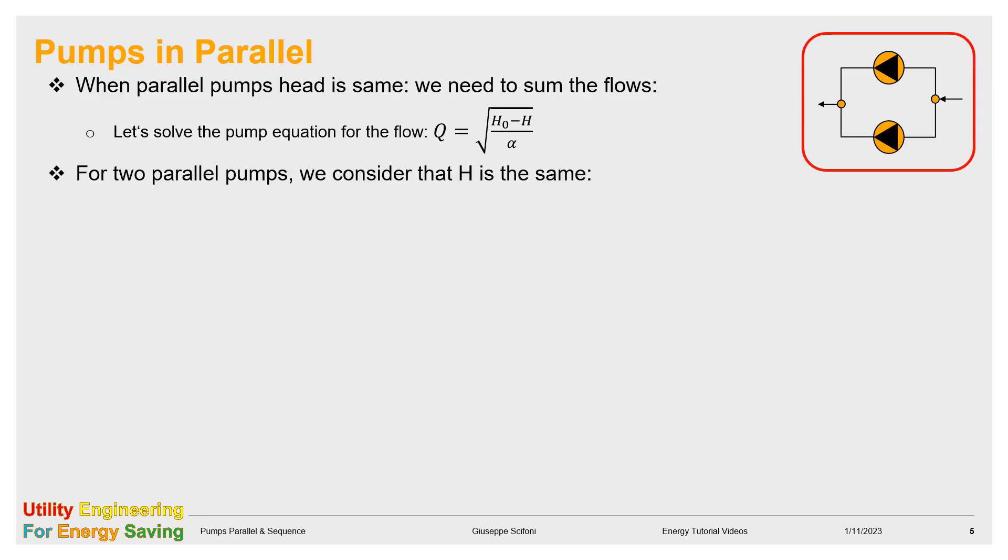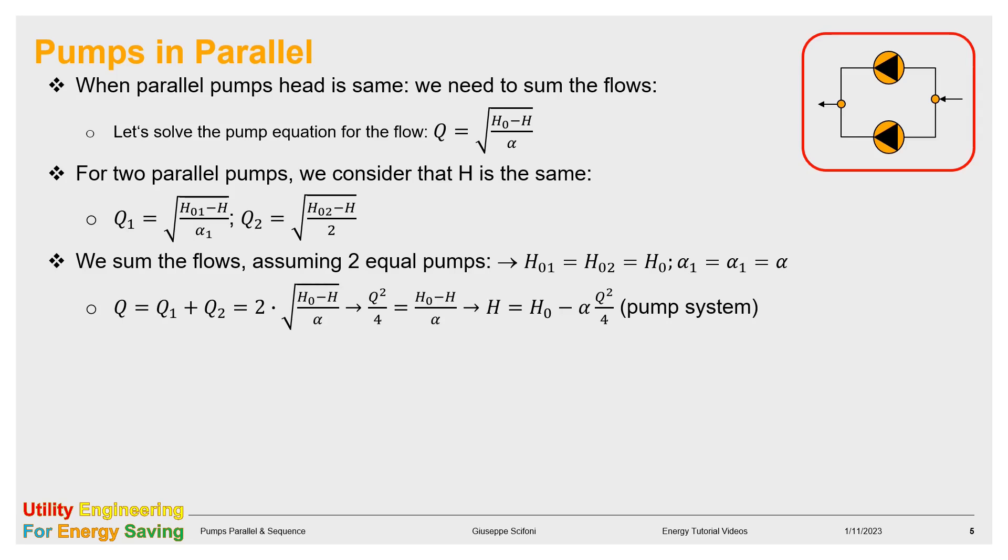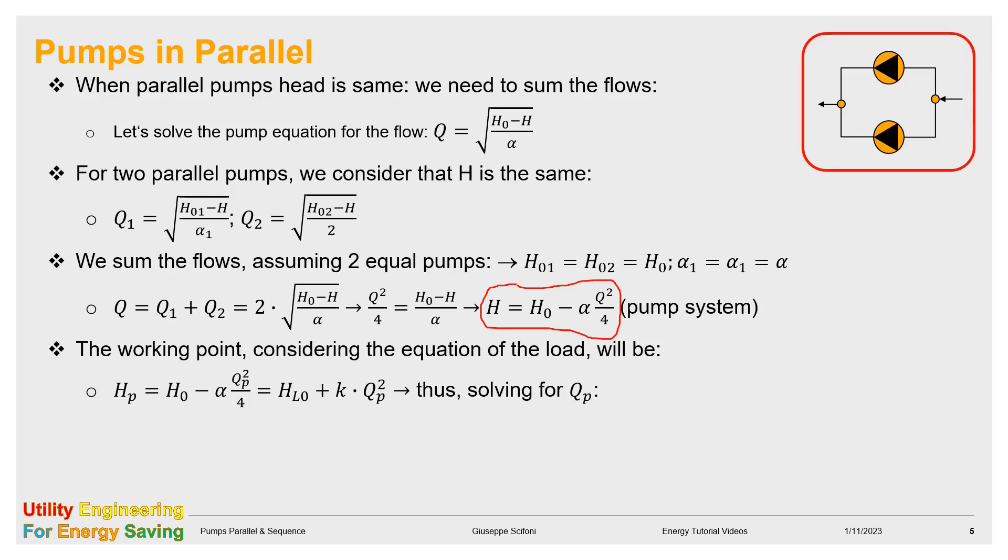Being two parallel pumps, then we write the same equation twice. If the pumps are equal, the subscript becomes the same. Adding the flows means to duplicate them. Now, we solve the equation for H back, and we obtain the expression of the pump system. The working point, as seen for the sequence operation, is found by the intersection of the load curve with the new pump system curve. The expression of QP and HP, the flow and the head for the parallel, are displayed in red. That is the case of two equal pumps, as said. Should be N equal pumps, the expression of QP becomes the one at the very last row.